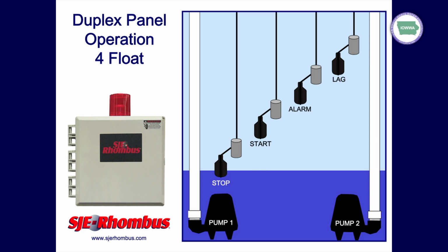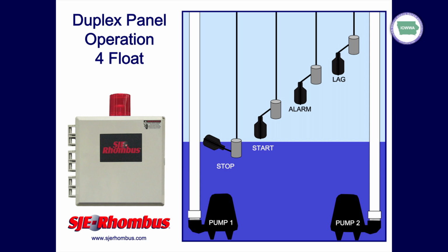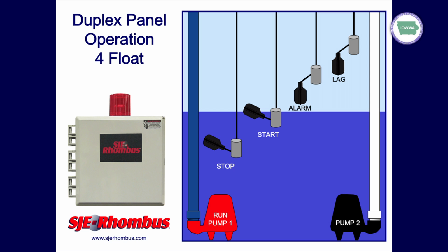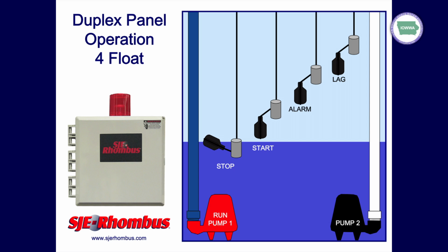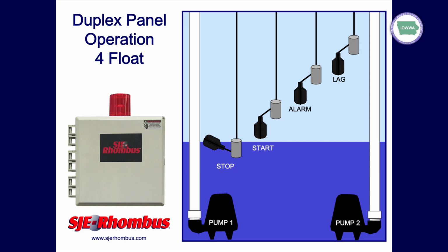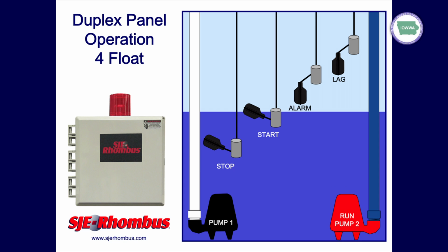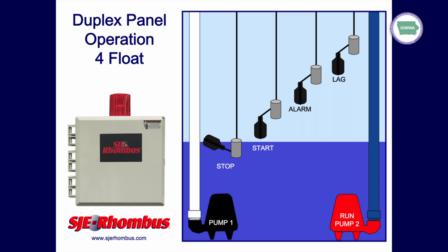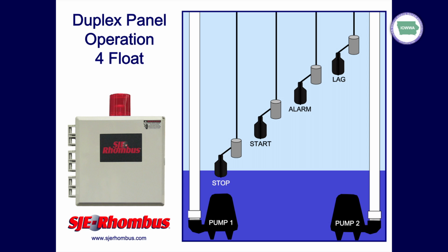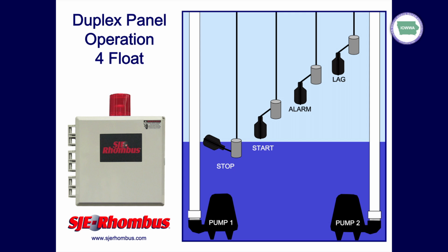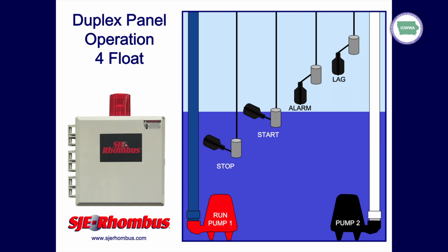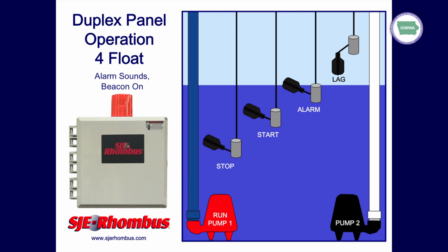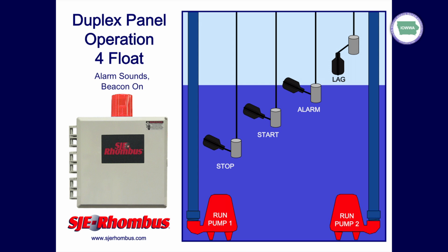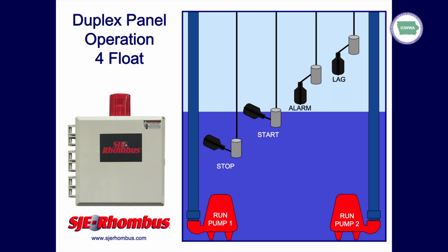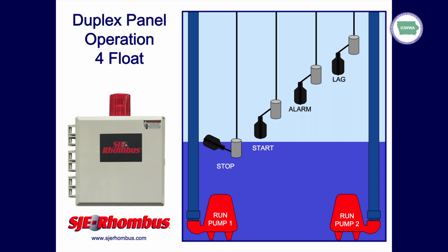Normal operation, we're going to have the stop float go up. Nothing's going to happen. Start float goes up. Pump number 1's going to run. It's going to alternate to pump number 2, just like we did with the 3-float situation. If the alarm float's reached before the lag pump float, it's possible the alarm's going to go off for a little while. Pump number 1's going to go ahead and take care of the situation, pump the liquid level down until the pump shuts off. Once we reach the lag float, both pumps are going to come on and run simultaneously.